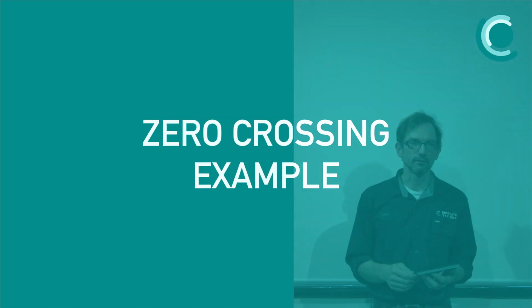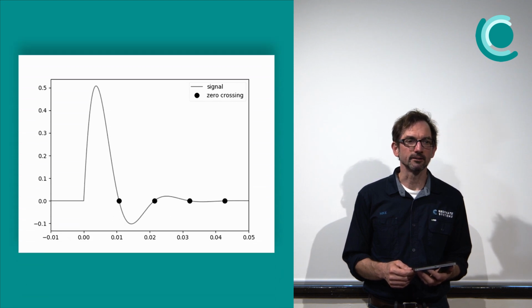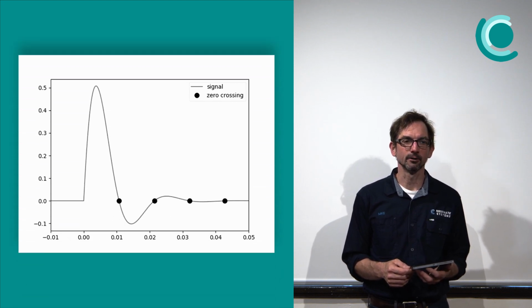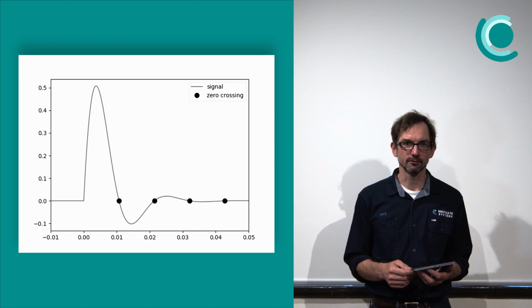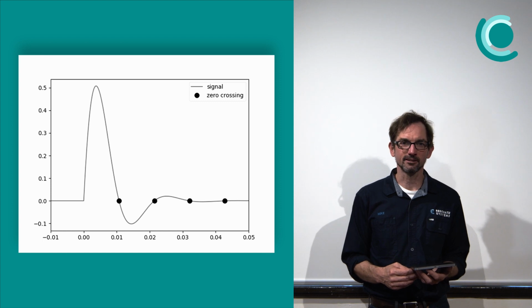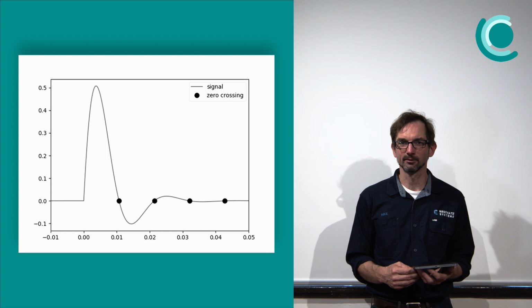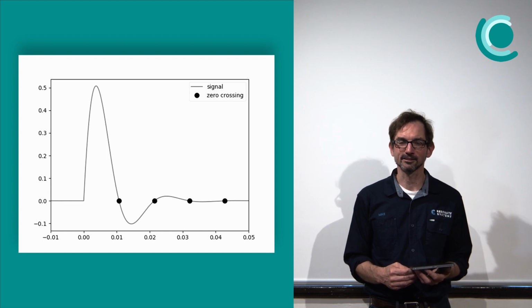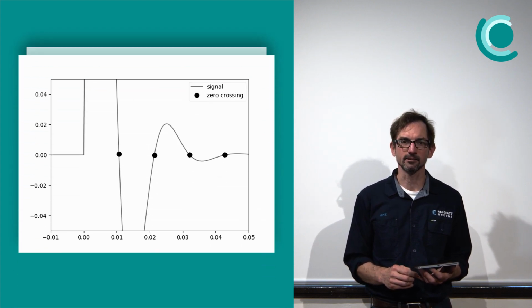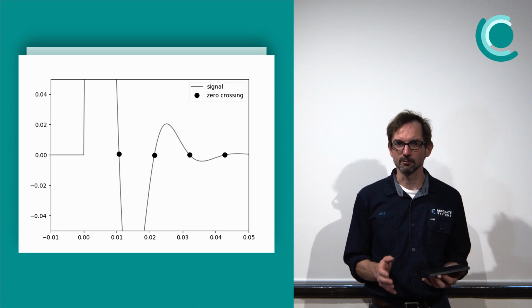So when you look at the zero crossings in that way, you can see from this figure that depending on the sample rate, your idea of where those zero crossings occur can be quite different. Now, admittedly, when I first did this at exactly 50 Hertz, because all of my signals are lined up and phase matched effectively, they all gave the same answer. They could all pick out the zero crossing because the zero actually happened at exactly the same place on all the signals. But I tweaked the frequency slightly for the purposes of this demonstration.